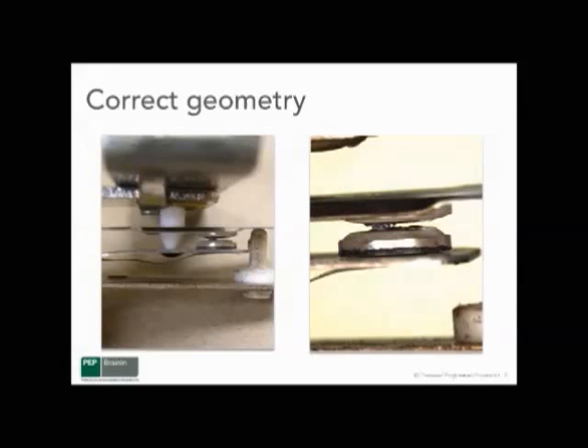Using the correct geometry for a contact is also an important consideration. When you use a radius contact — in some cases a radius and flat, or two radii — you have an opportunity to make contact near the center of both contacts. This is preferred because you'll have the best situation with regard to thermal conductivity, moving heat away from the contacts. You'll also be able to discourage arcs from forming at the edge of the contact, since sharp corners can provide a preferential area for arcing. Try to choose the correct geometries and have the contacts aligned properly to make contact near the center of each contact surface.